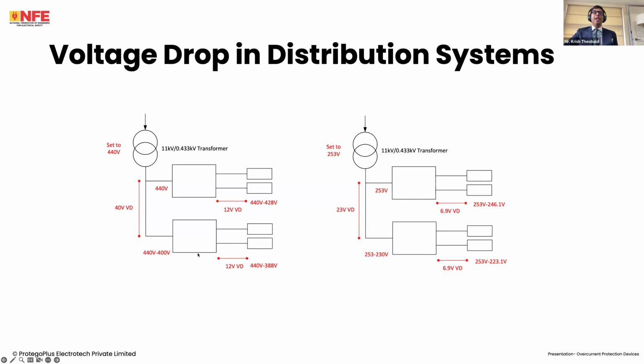First thing, remember the idea is that the furthest point receives the voltage, because as the length increases, the voltage drop increases. So what do I do? I set the transformer first. This is the same transformer; I'm just considering three phase here and single phase here, to the highest possible setting given the tolerance. So for a 400 volt circuit, multiply by 1.1: 440 volts. Set this transformer to 440 volts. And then I have a possibility of receiving between 440 to 400 volts here.